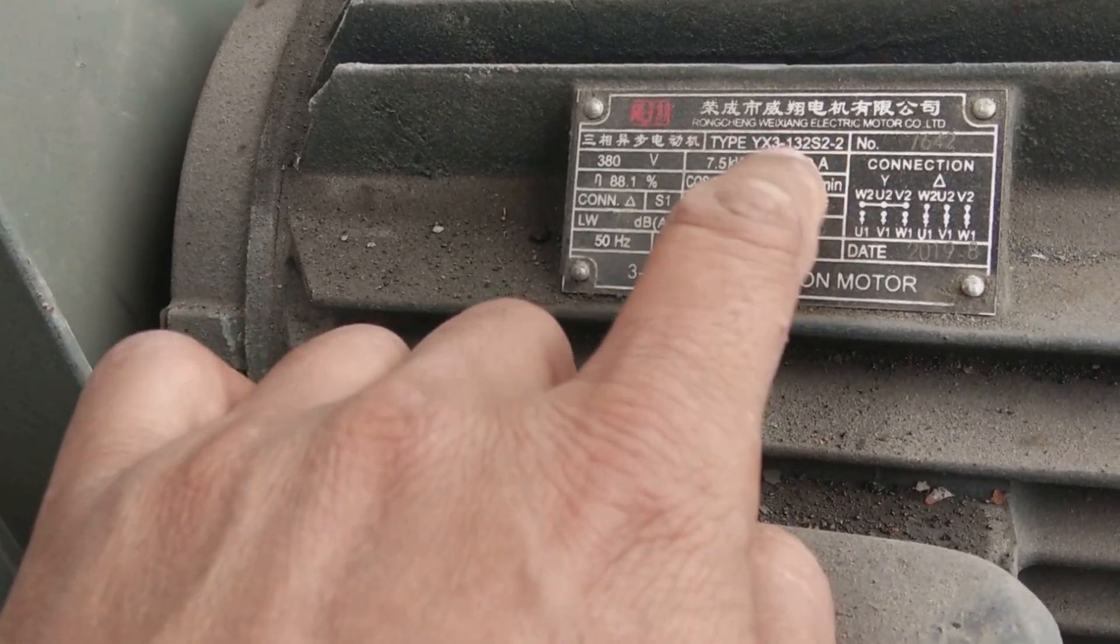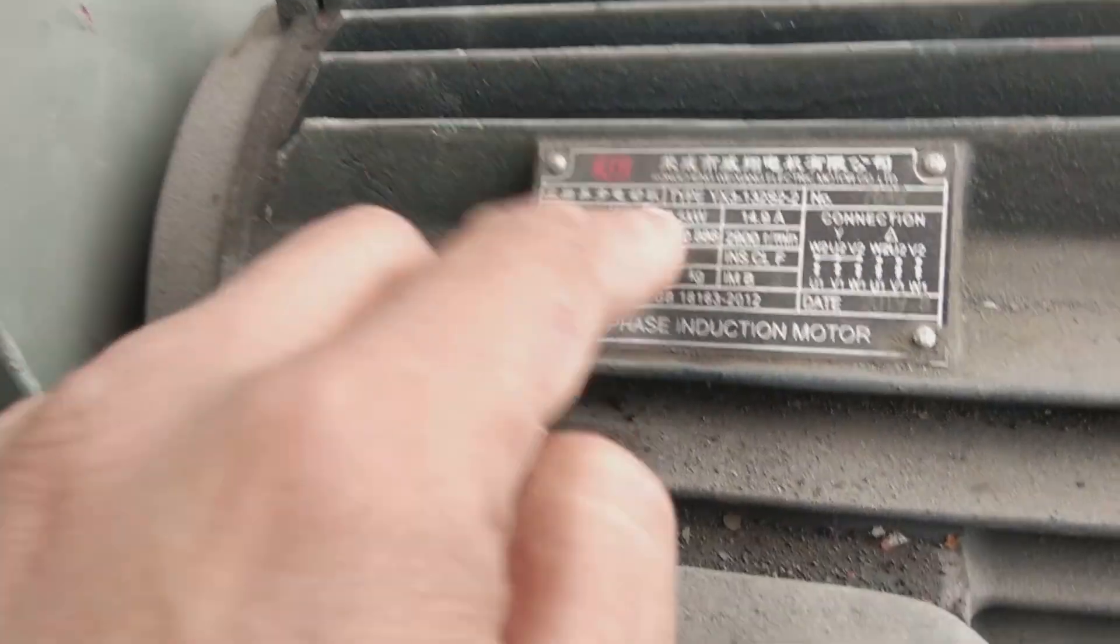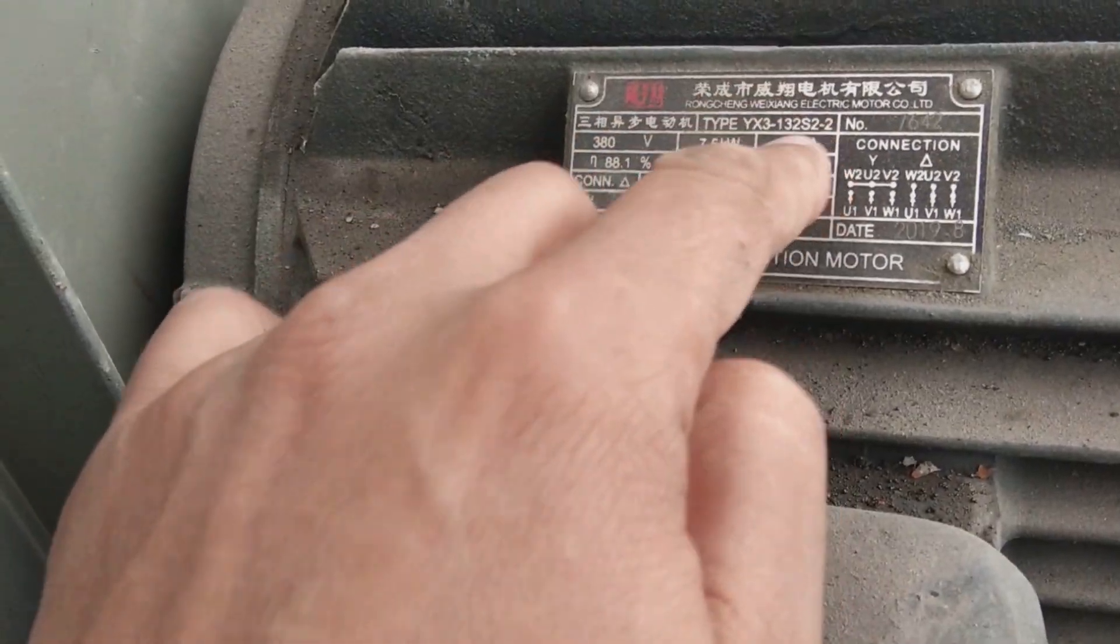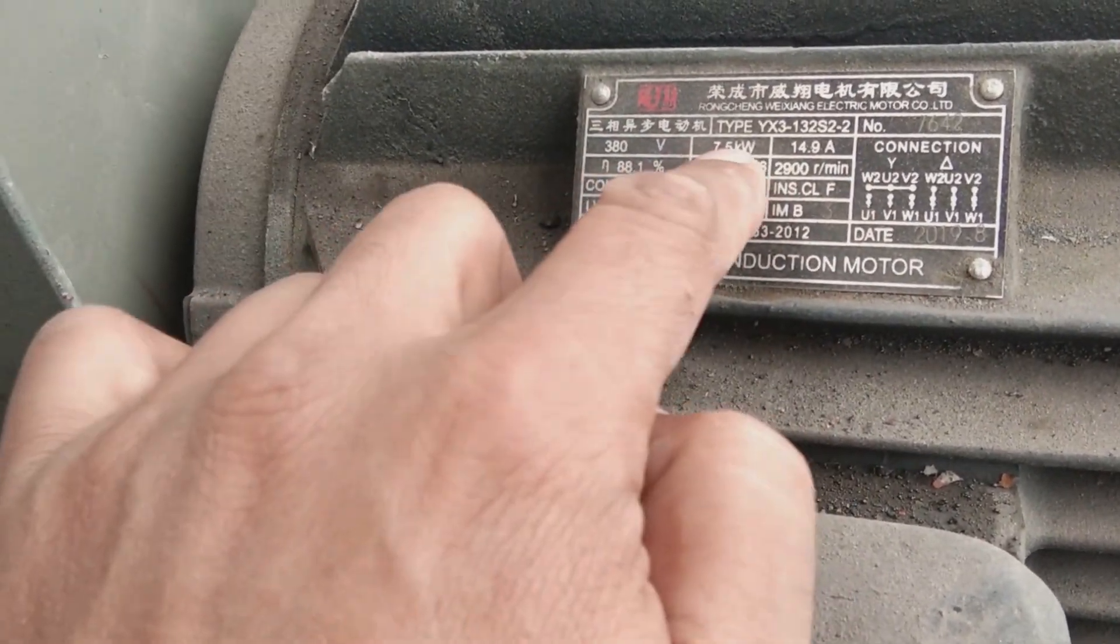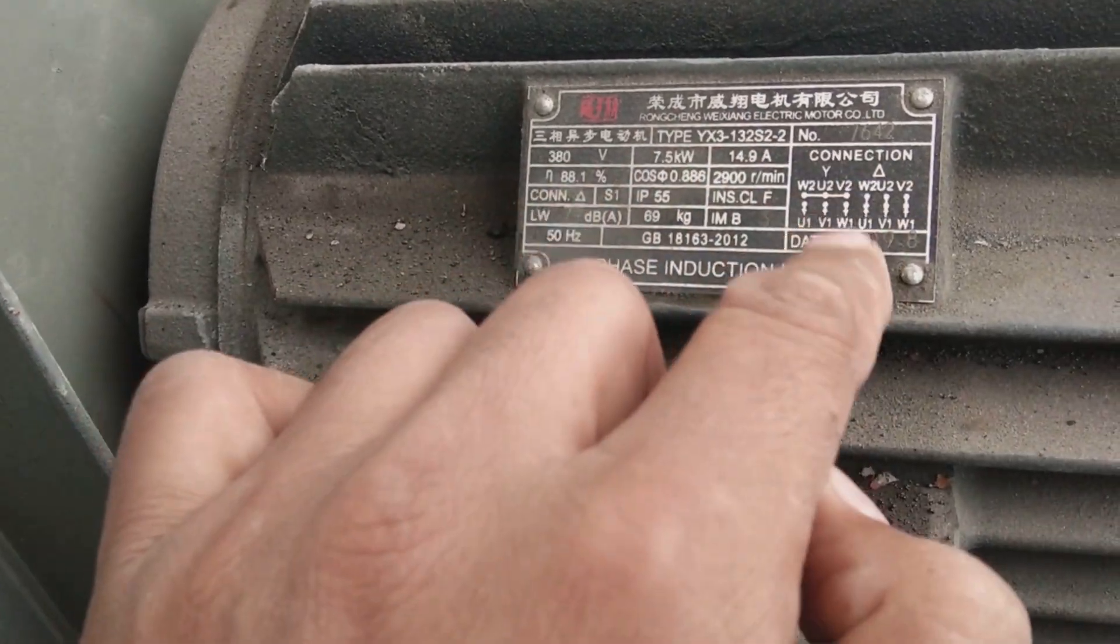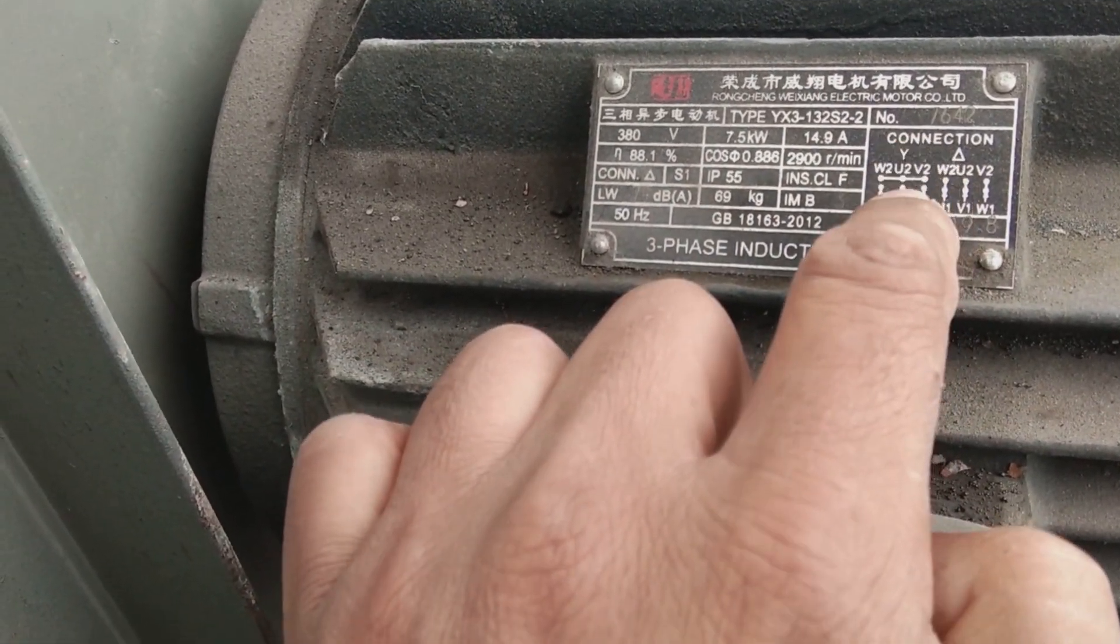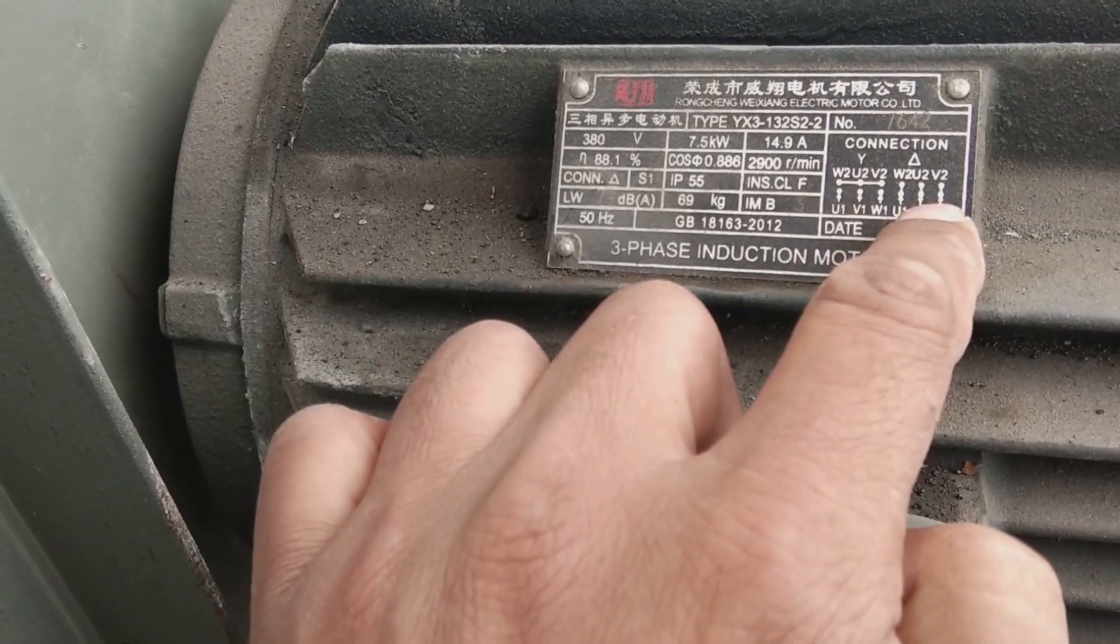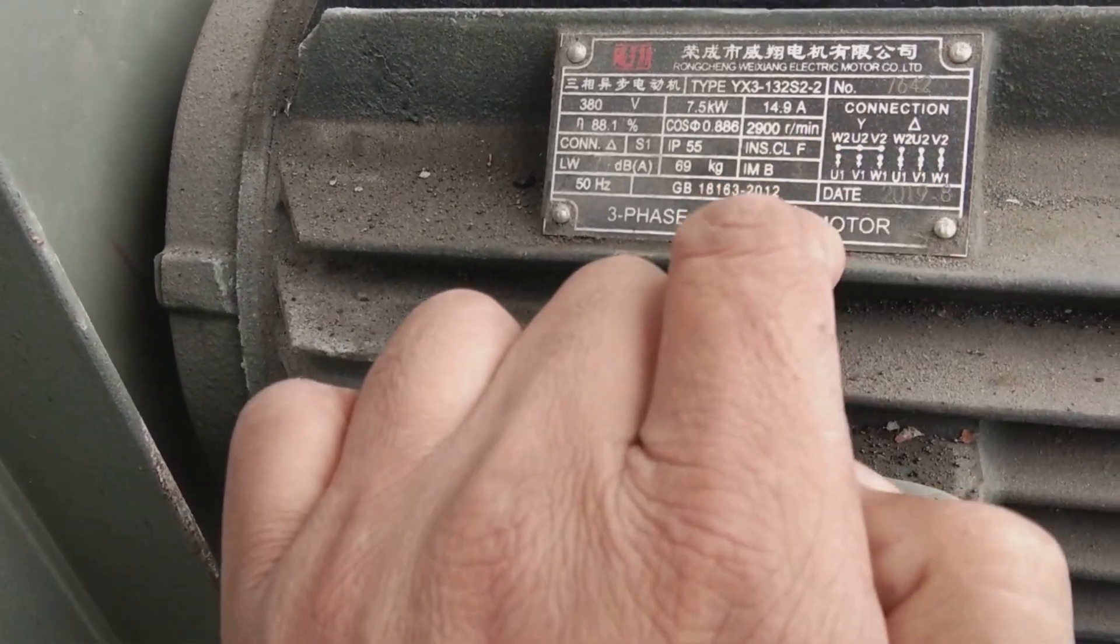There's a rule of thumb: if the frequency is 50 Hertz, the current will be simply double the kilowatts. So if the kilowatt is 7.5, around 15 ampere is expected, which is 14.9 in this case. Here you see diagrams - this is star and this is delta.